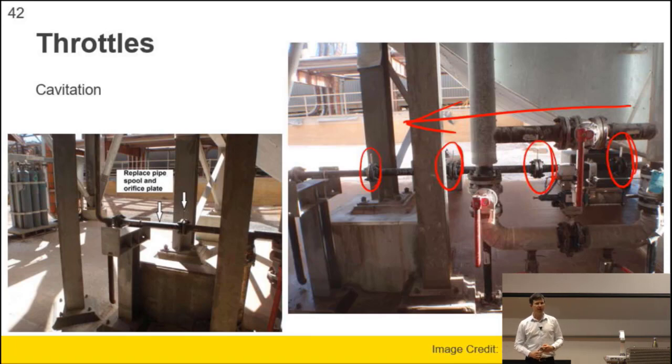Do you end up wearing out the orifice plate? Only if you've got particulate matter in the fluid stream. So if you've got relatively pure water, not very much. You don't get much wear, but yes, you would slowly round off and then increase the diameter of the orifice. But that happens far slower than cavitation destroys things. You also see cavitation at the inlet of a pump impeller because it's drawing liquid in, spinning it out, and so you get low pressure points at the inside of that. So yeah, cavitation will destroy your kit much faster than wear. Yeah, go.